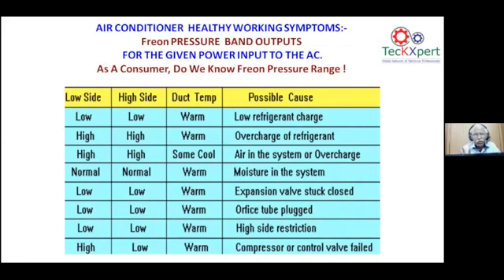You need to have the Freon gauges on each and every one of your ducted units, all your package units, and all your smaller size ACs also. You can fix these gauges to know whether the Freon pressures are okay and you are maintaining correctly. By any chance, if you are overcharging, the consumption also goes up, and again the duct temperature is warm. Or there is air in the system, especially on the refrigeration line. This also can cause malfunction of the air conditioning, especially on the Freon side.